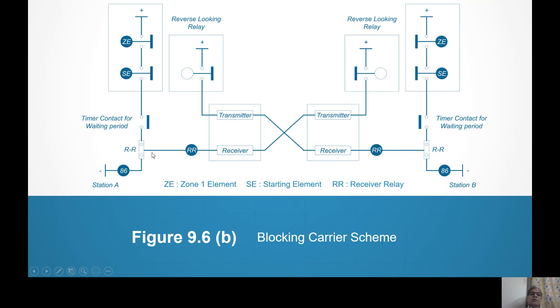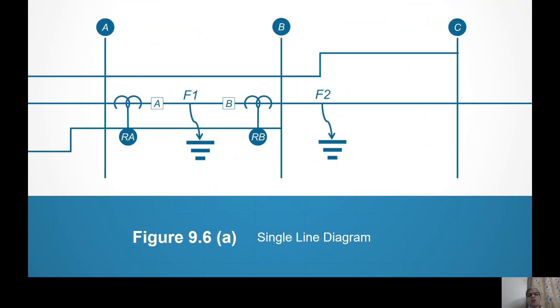So the NC contact of RR will open out before the timer contact closes. RR opens, so relay 86 cannot be energized and the circuit breaker at end A cannot trip. At end B, in any case the breaker is not opening because the fault is not within its range. This is a blocking scheme — the carrier signal is blocking the operation of relay A. Therefore this is known as the blocking carrier scheme.